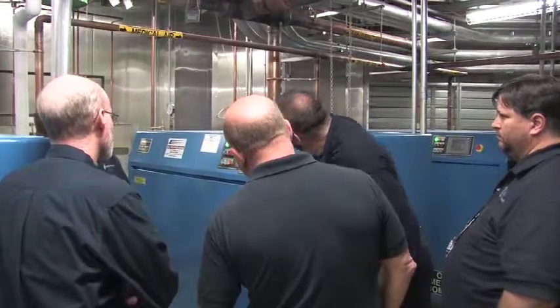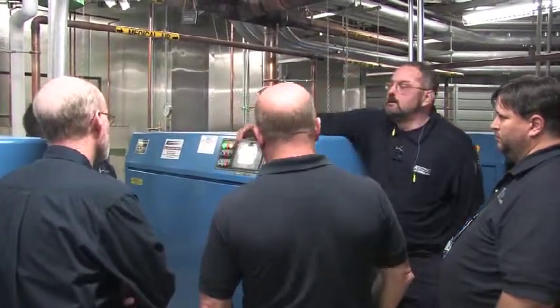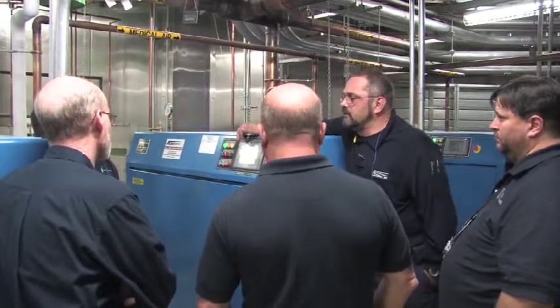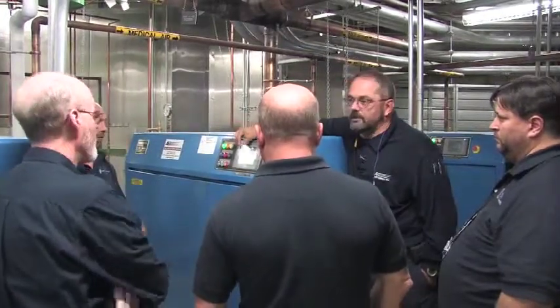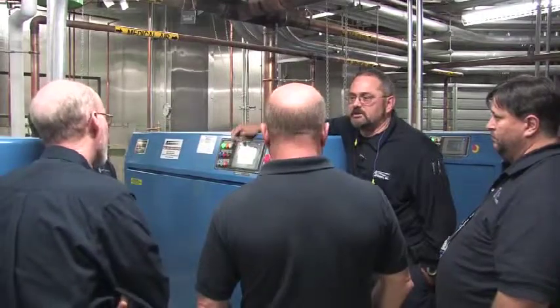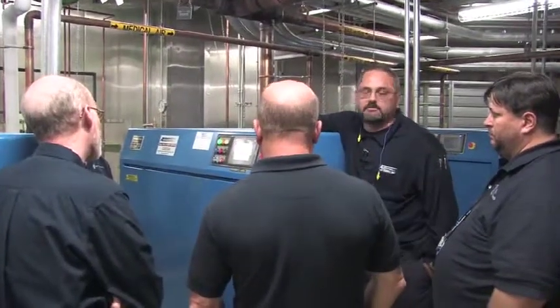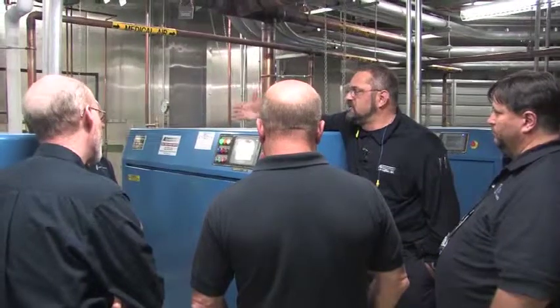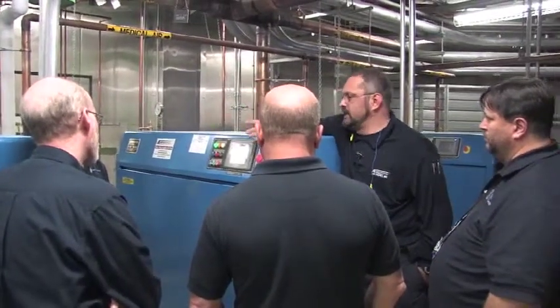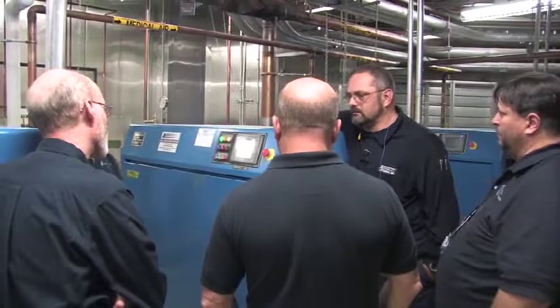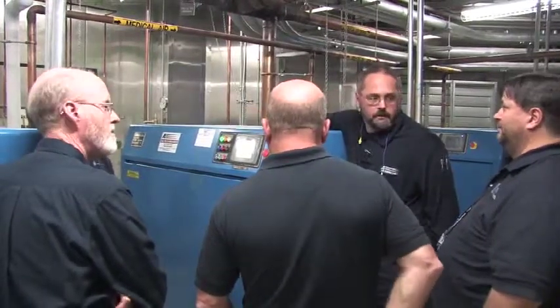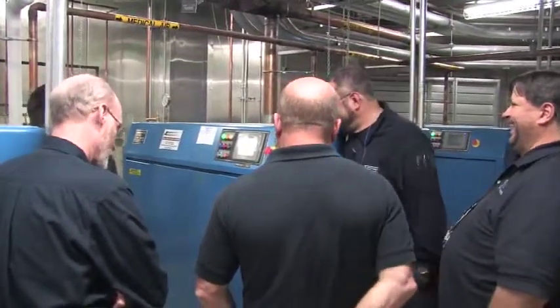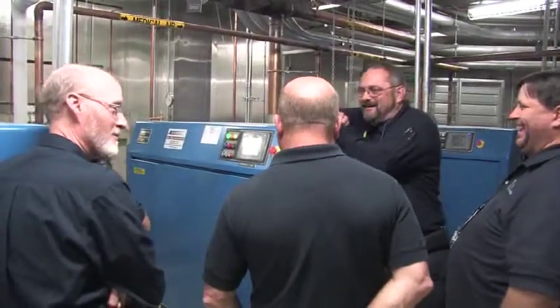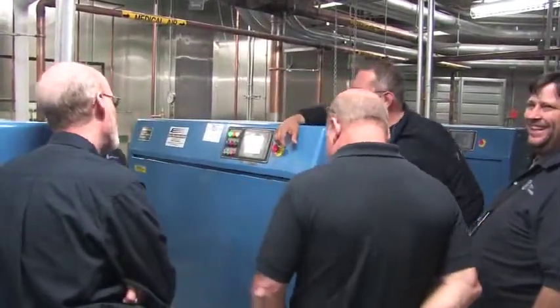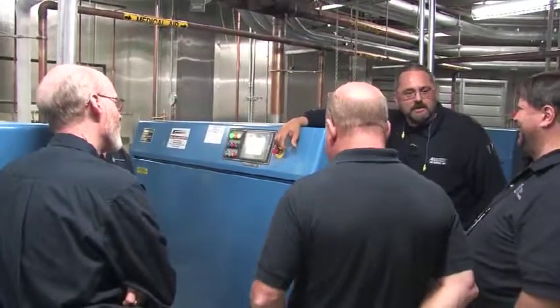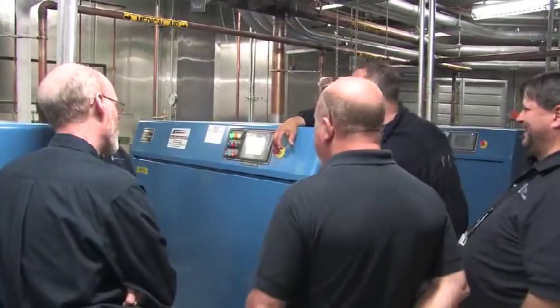This one's your hours and your cycles. You probably know the running hours and loaded hours, and the most critical thing on these is the cycle times, how many times the inlet is opened and closed, because these machines have three states: off, running unloaded, and running flat out. Or broken, well, that would be off. That would be, you know, you have a hard reset. That's a hard off.